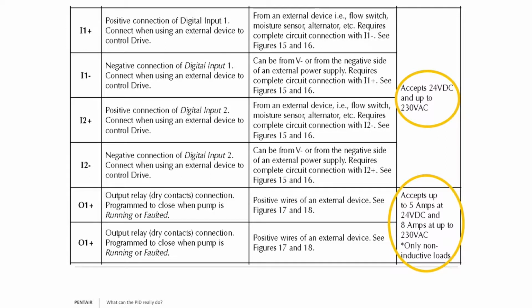Now, it accepts up to 5 amps, either DC, 24 volt, or up to 8 amps on 230 volt or 115, but it's a non-inductive load. It's not intended to be a relay to start a pump. If you do so, you will damage the actual contact.